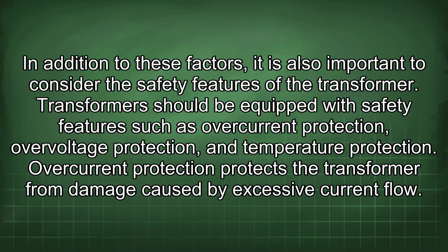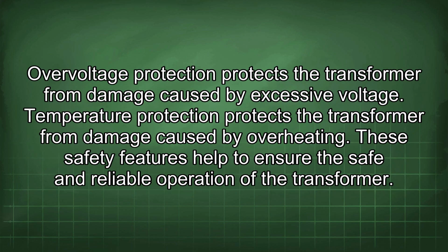In addition to these factors, it is also important to consider the safety features of the transformer. Transformers should be equipped with safety features such as overcurrent protection, overvoltage protection, and temperature protection. Overcurrent protection protects the transformer from damage caused by excessive current flow. Overvoltage protection protects the transformer from damage caused by excessive voltage. Temperature protection protects the transformer from damage caused by overheating. These safety features help to ensure the safe and reliable operation of the transformer.